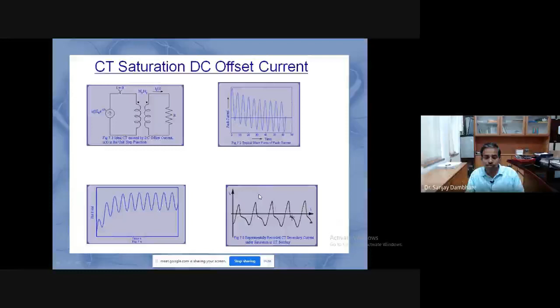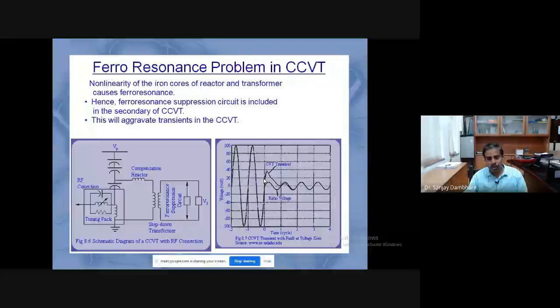The subsidence oscillations are present for a very small time, and this puts the protection engineer under stress, because you are giving wrong information to the relay and the relay will maloperate. These oscillations generated because of ferro resonance are to be handled or addressed well in order to have a correct protection decision.